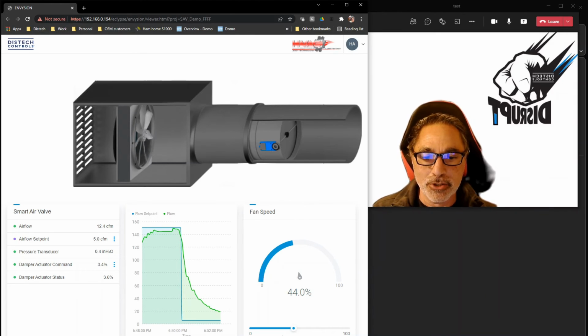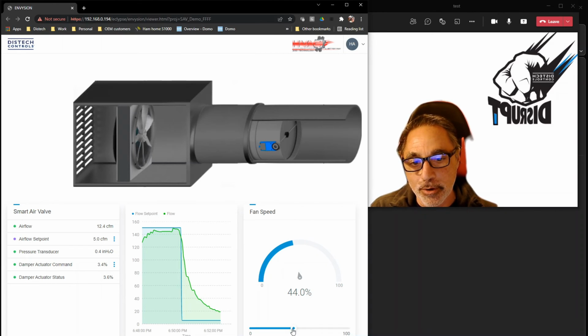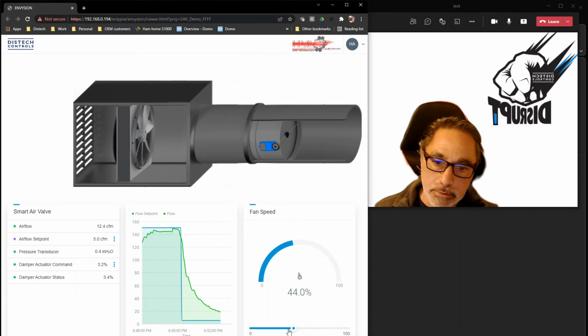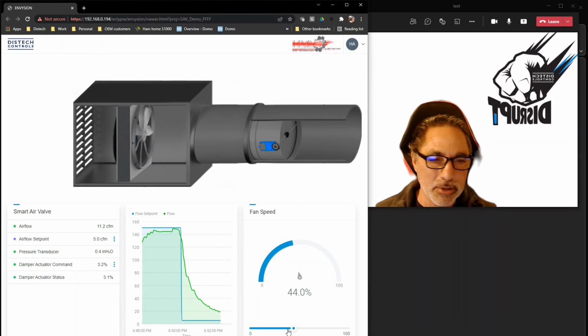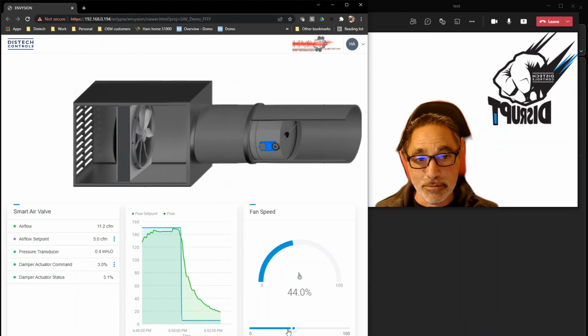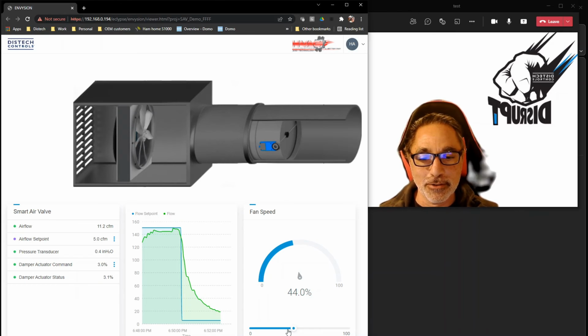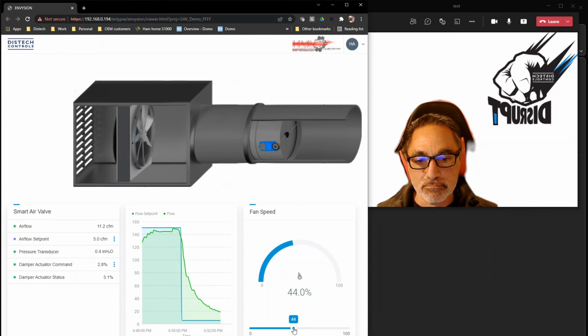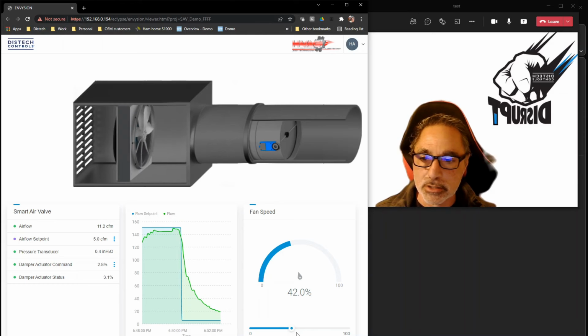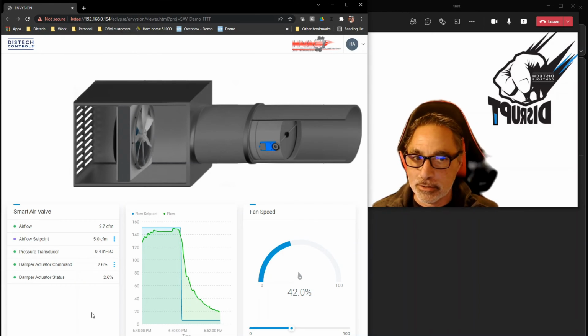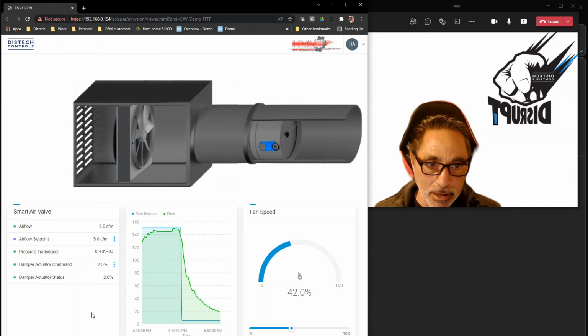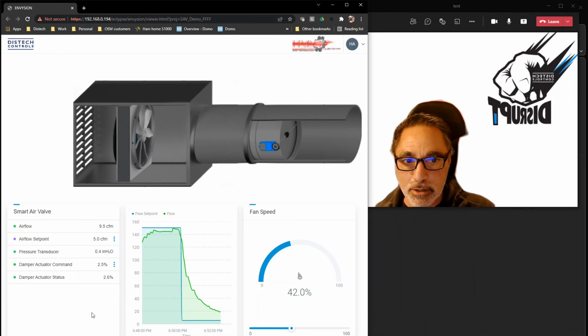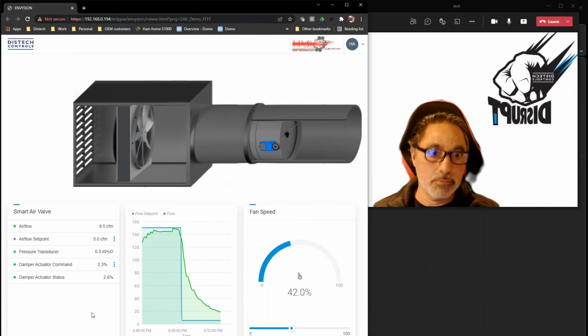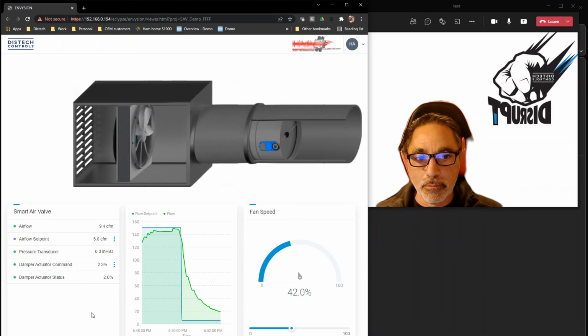Again, I'm actually controlling the airflow here. We're at about 44%. It's probably definitely pushing about 120, maybe 150 CFM through. Obviously, I don't have that in front of me. It's in my basement. It's right below me. I could drop it down a little bit more just to see if it drops this a little bit faster. And even if I'm doing that, all I'm doing is just slowing the speed of the fan down, and obviously the communication of VAV boxes or the smart air valve to the actual primary equipment.